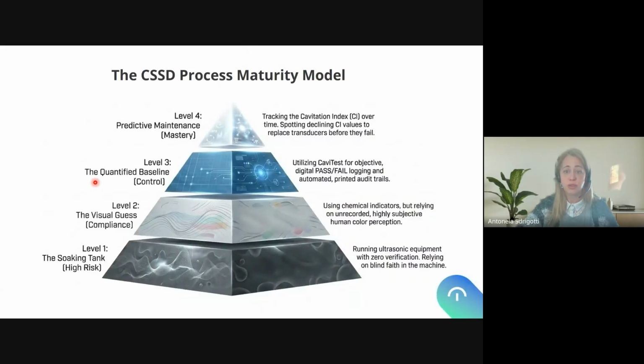We are under control. We are utilizing the CaviTest for objective digital pass-fail logging and automated printed audit trails. And if we want to go to the top, to level 4 with predictive maintenance, gaining mastery in our monitoring, tracking the cavitation index over time will help me spot declining cavitation index values and replace transducers even before they fail.